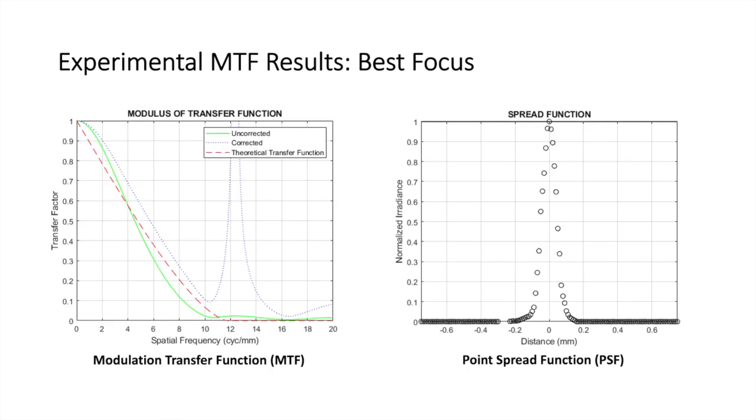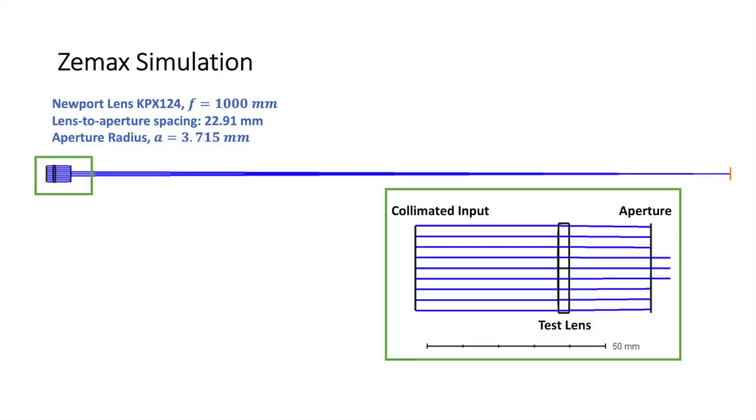Furthermore, the program calculates the MTF for the experimental cutoff frequency, the raw data obtained from the LSF measurements, and the transfer function accounting for the diffraction effects of the slit, or the slit transfer function. The point spread function is also included.